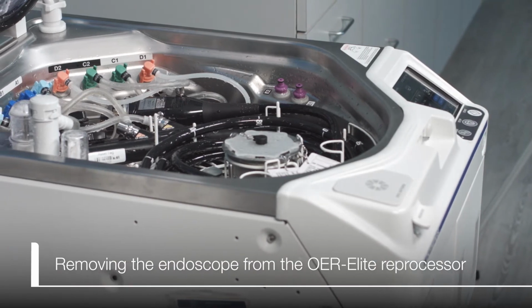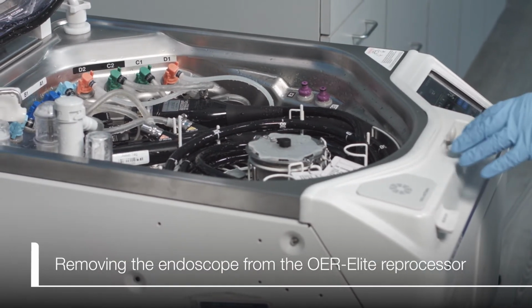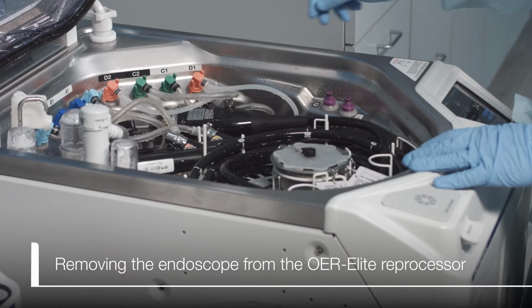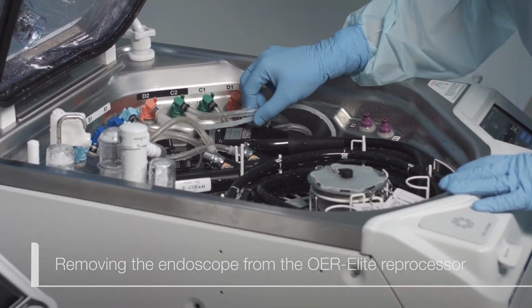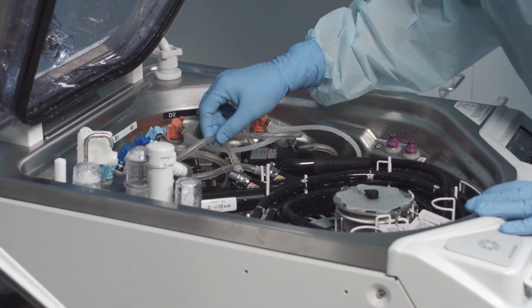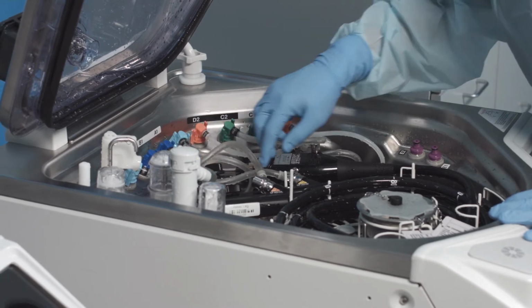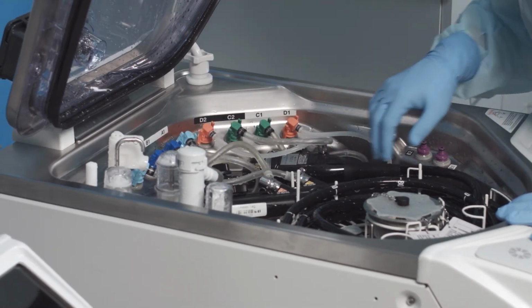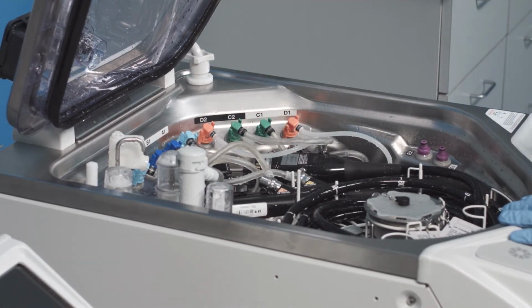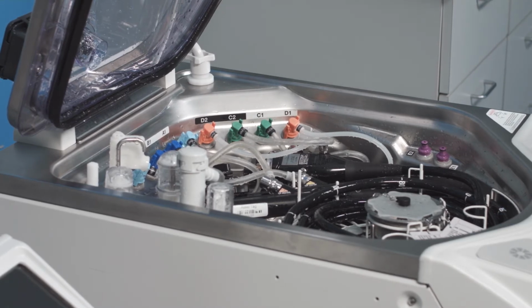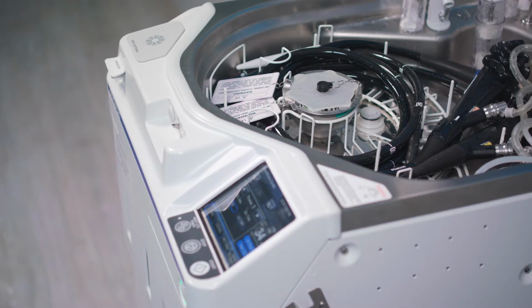Prior to the endoscope being removed from the OER-Elite reprocessor, it's important to check that the connecting tubes are not kinked or disconnected. If any connecting tubes are bent or not properly connected to the OER-Elite or the endoscope, please reprocess the endoscope again to ensure proper cleaning.